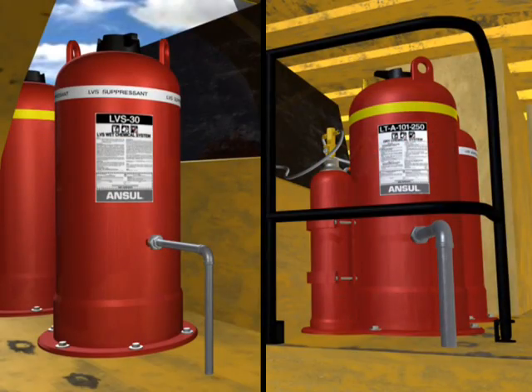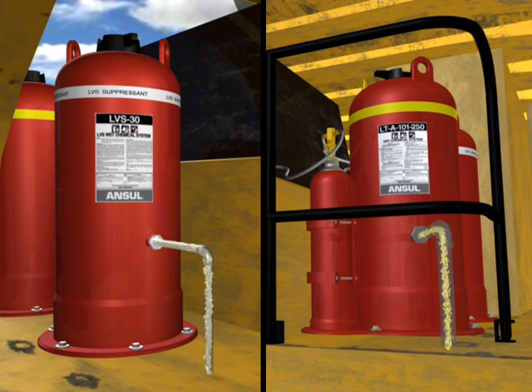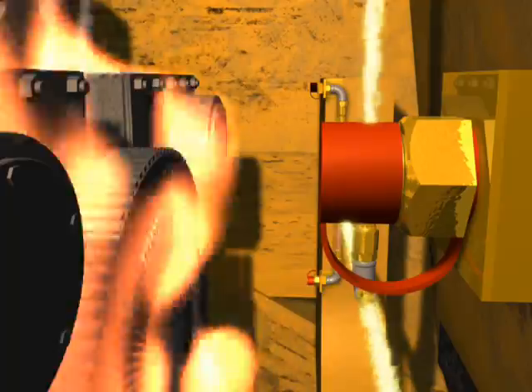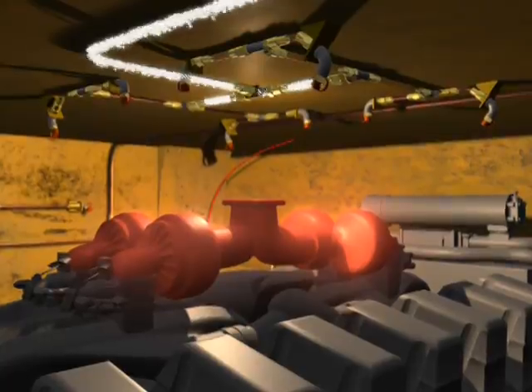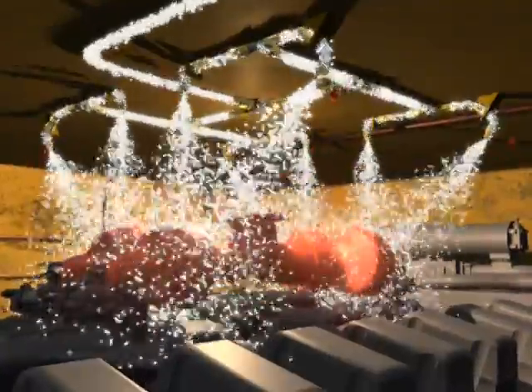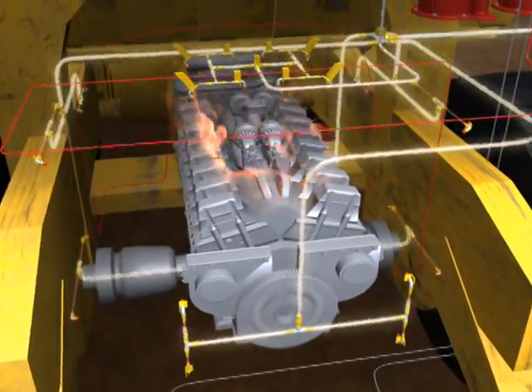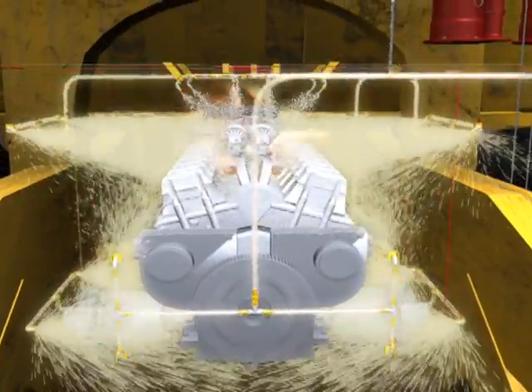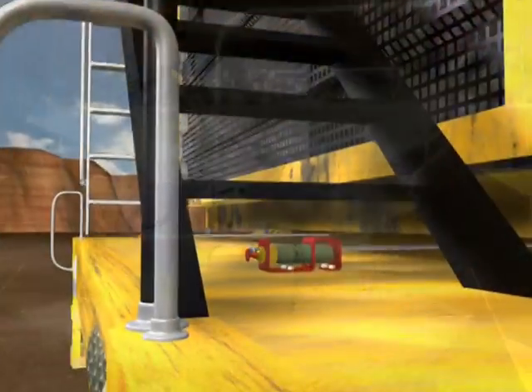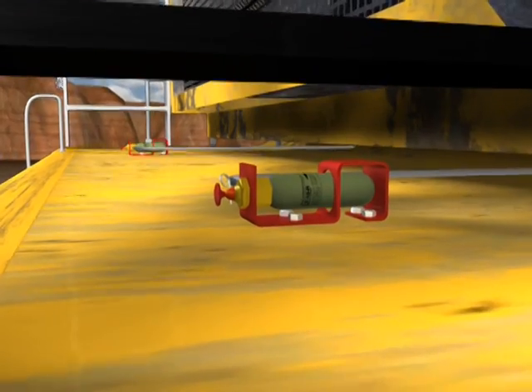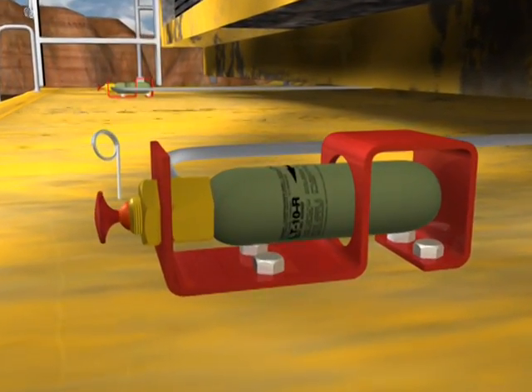In the case of the LTA-101 LVS twin agent system, the FORAY dry chemical and LVS liquid agent systems are simultaneously deployed. The FORAY dry chemical agent discharges through fixed nozzles aimed at specific hazards, flooding the area to quickly control and suppress the flames. Meanwhile, the LVS liquid agent quickly cools the hazard area, helping to prevent the possibility of fire reflash. The twin agent combination is fast and effective, suppressing the flames of a fire and cooling the hazard area. As backup, the system can be actuated by one of the many manual actuators along the path of egress.